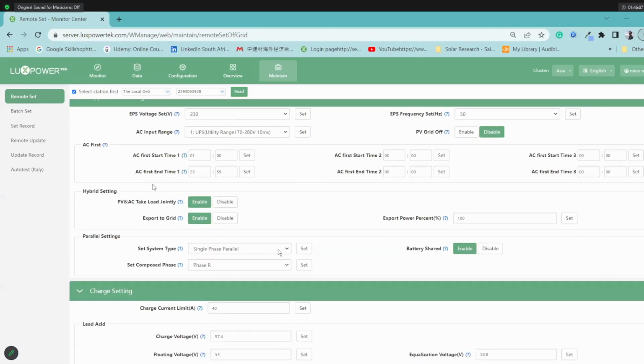With that Eco hybrid inverter, it's primarily an off-grid inverter with partial hybrid functions. There is no internal and external CT, meaning the moment you turn on your hybrid settings and export to grid is disabled, there will always be a slight backfeed that you cannot control. If your client has a prepaid meter that's quite sensitive, which is most of the new ones nowadays, it will cause the prepaid meter to trip.